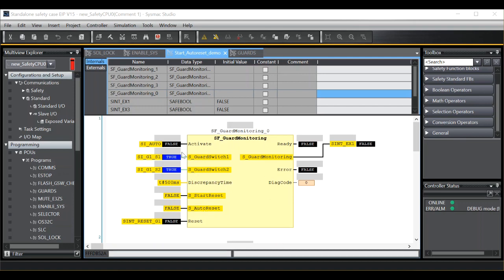Upon transition of the activate signal on the function block, I would expect the safety guard monitoring output to stay at a false condition until the reset button is pushed. So in effect, the block will be working continuously in a manual reset capacity.